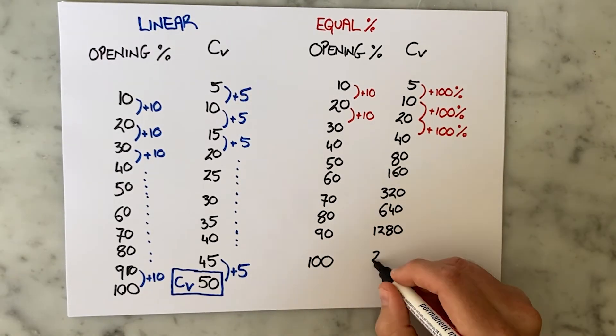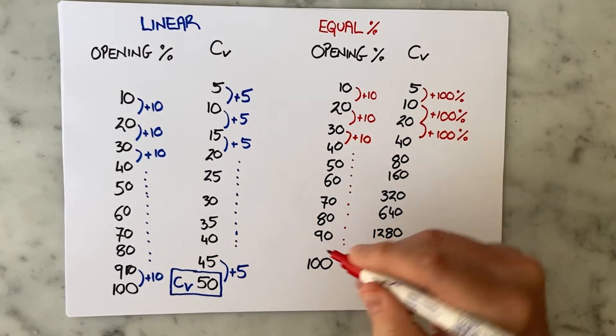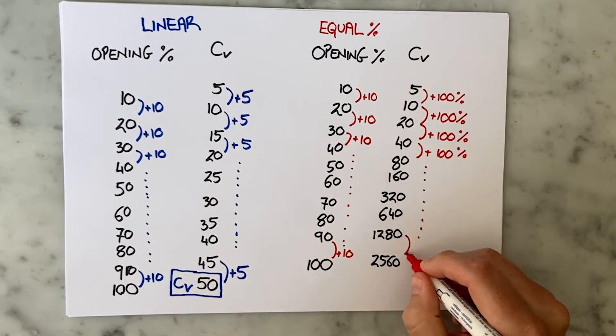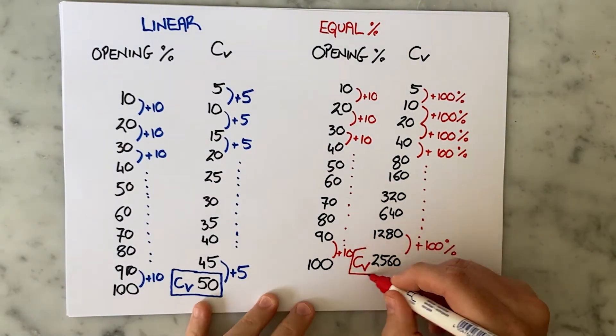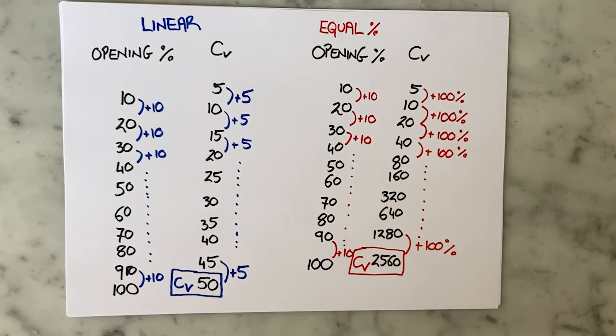If I carry on like this I will get to a valve CV at 100% opening of 2560. If you're thinking wow this is growing exponentially, then you are correct in the technical sense. This is an exponential curve. So this is a really big valve.